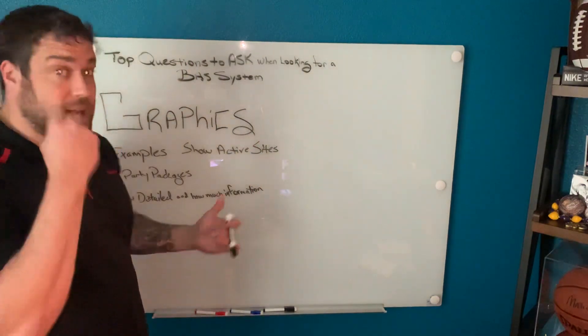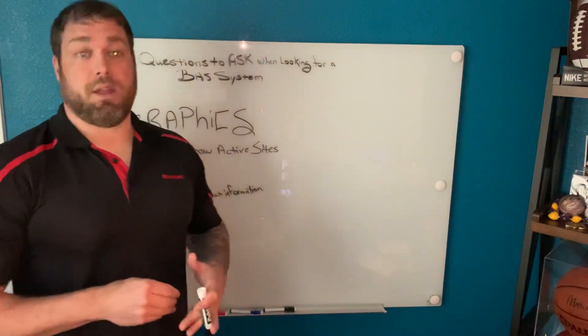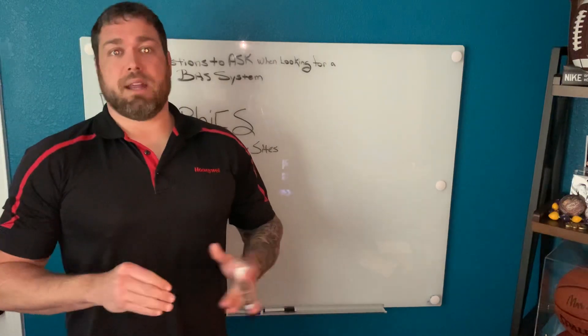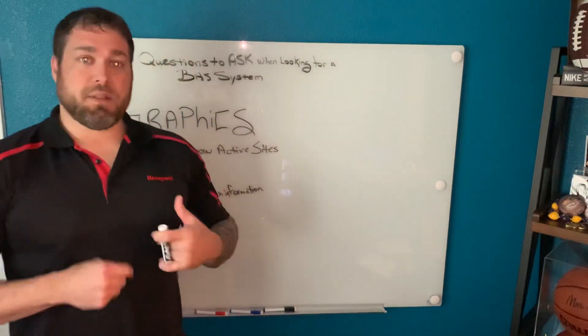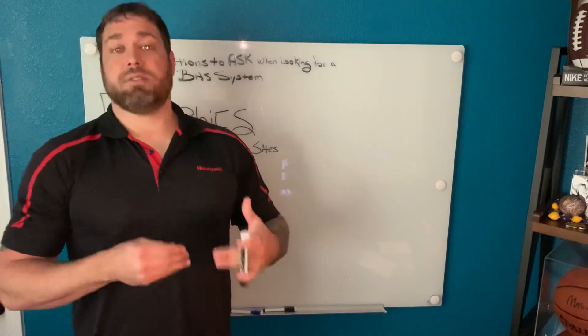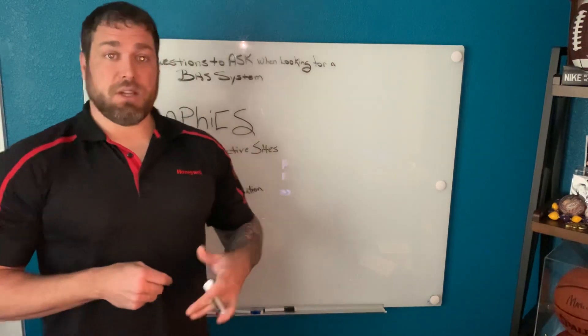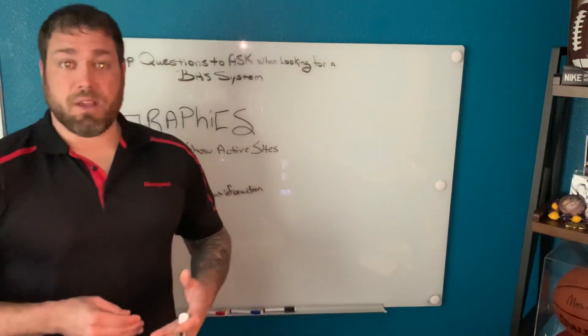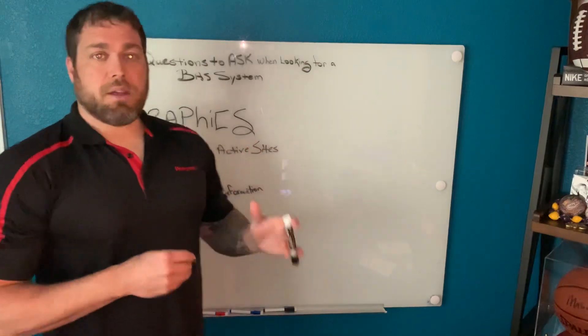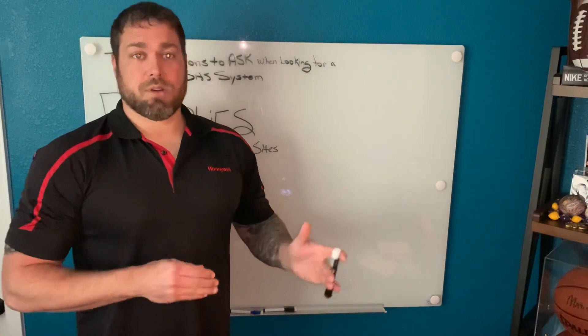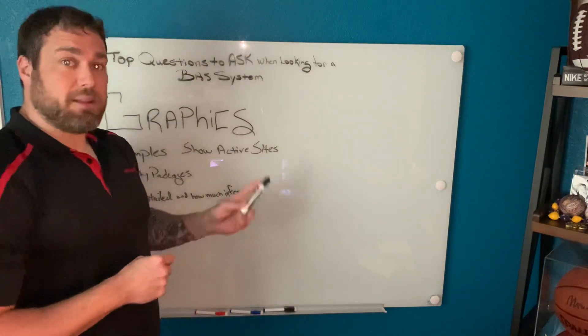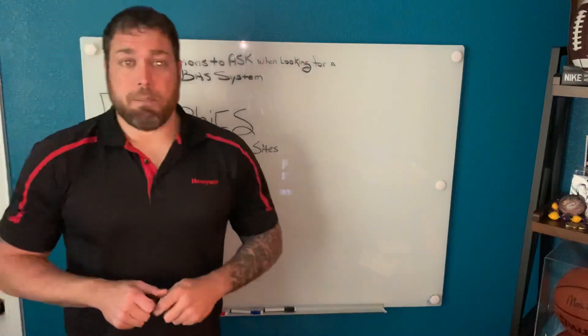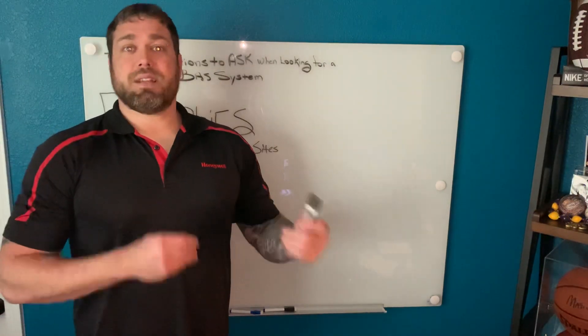The next question is, how detailed and how much information are you wanting? We've done sites where we have literally every point in a chiller on a page, because the engineers in that building actually take care of all the low-pressure machines and they really need all that detailed information. It all depends on what you're looking for at the end of the day. But the biggest thing I find is people are paying a lot of money for these third-party packages when a building doesn't necessarily need it.